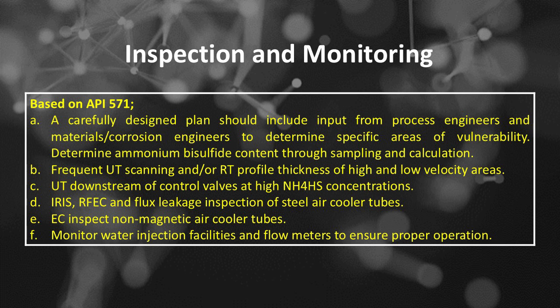Number D, IRIS, RFEC and flux leakage inspection of steel air cooler tubes. Number E, EC inspection of non-magnetic air cooler tubes. Number F, monitor water injection facilities and flow meters to ensure proper operation.